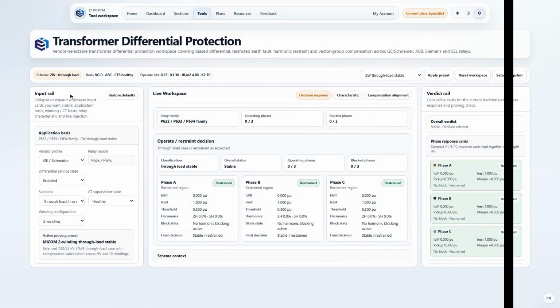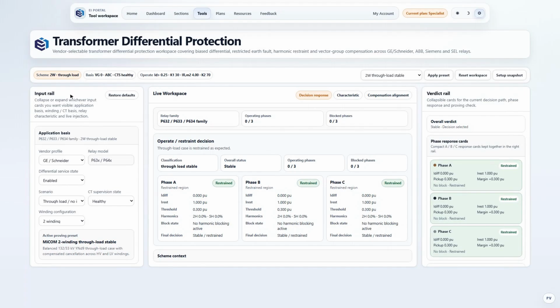Transformer differential protection has one of the hardest jobs in the substation. Stay perfectly stable through load and external faults, operate fast for an internal fault, and refuse to be fooled by magnetizing inrush or overexcitation. This workspace proves a real relay does exactly that, and everything you're about to see is driven from the relay's own manual-backed settings.